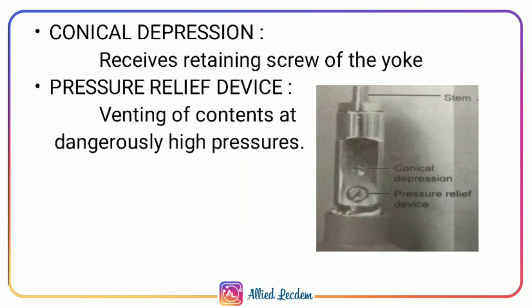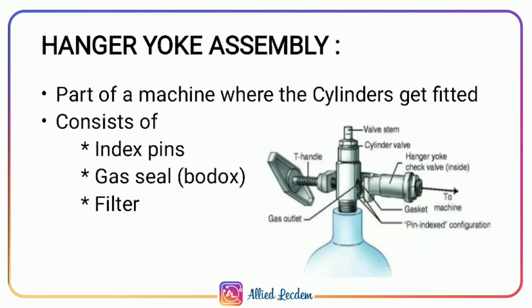The conical depression receives the retaining screw of the yoke. The pressure relief device allows venting of contents at dangerously high pressure. The hanger yoke assembly is the part of the machine where the cylinders are fitted — a special port for mounting of cylinders. It consists of index pins, gas seal, Bodok seal, and a filter. The Bodok seal, similar to a cooker gasket, provides an airtight seal preventing leaking of gases and is made up of neoprene rubber.